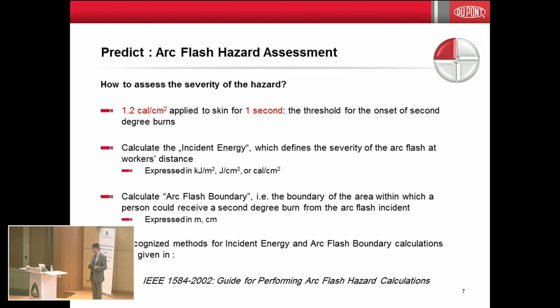So in order to do those calculations, a set of curves were developed by the colleague I was mentioning, Mr. Ralph Lee, and they have been put into a standard. Today this is still the only standard in the world that includes the curves allowing calculation, from an electrical system, of the incident energy and the arc flash boundary. This standard is the IEEE 1584.